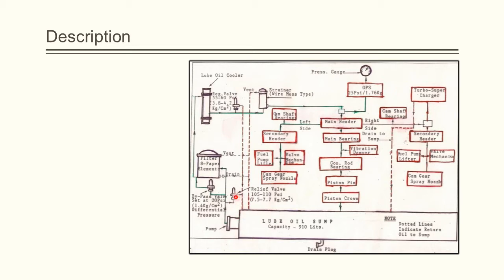From here, the remainder of the oil flows through the filter which is equipped with the differential pressure bypass valve to hold a relatively constant pressure across the filter. From the filter, the oil flows through the cooler which acts like a heat exchanger and then to the regulating valve and then to the strainer.